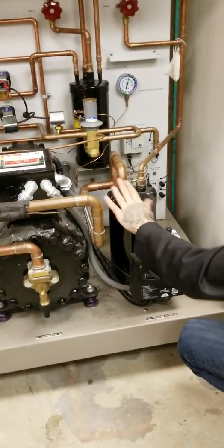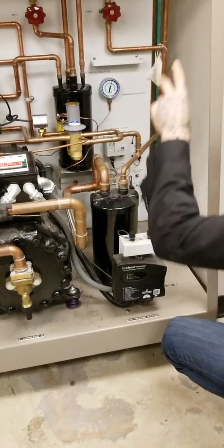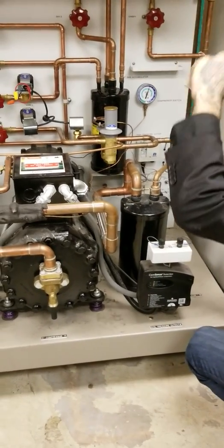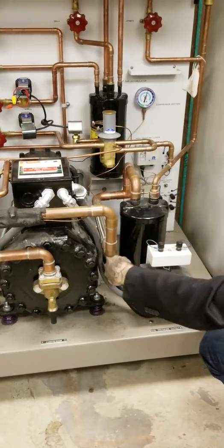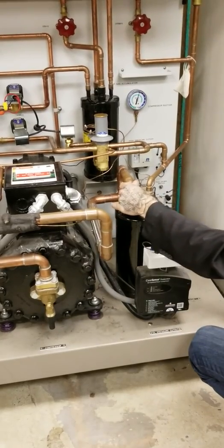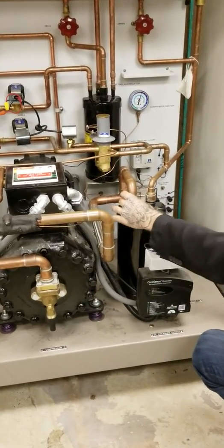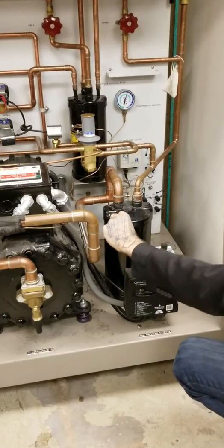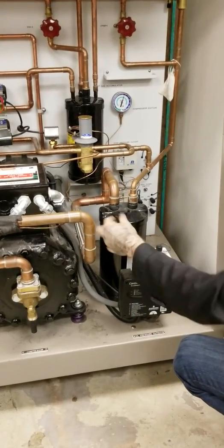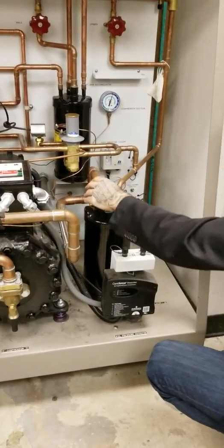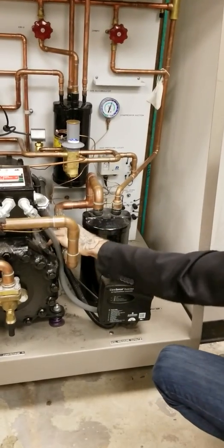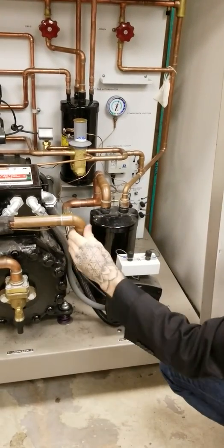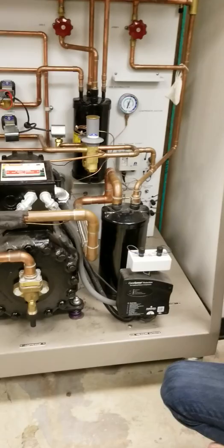You also have your liquid accumulator here. So if any liquid refrigerant is making its way out of the evaporator, it will be gathered in here, where you have another pipe that's not like a straw. It's more just going to be sucking right off the top, pulling the vapors off the liquid so that it could travel back, another flexible coupling, and then back to the compressor to restart the cycle.